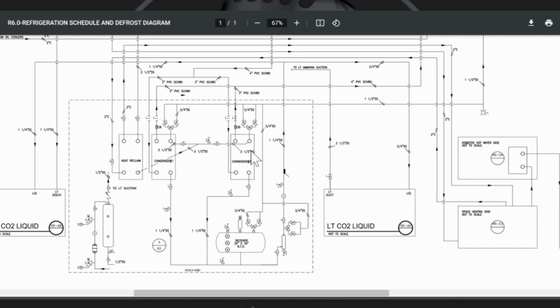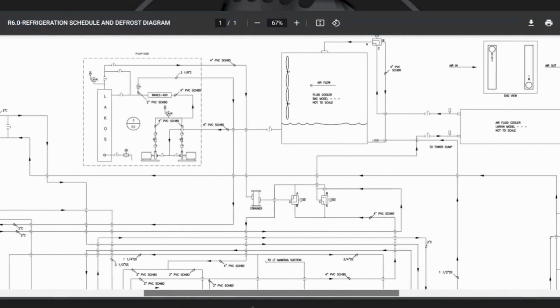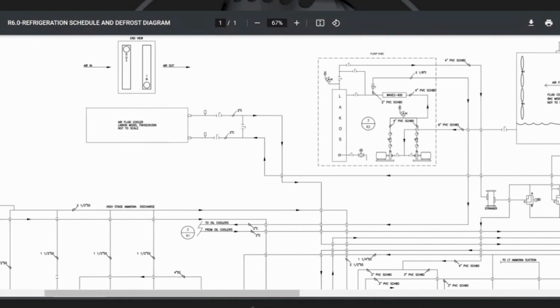So you basically vented it to the inlet of your condensers, I'm assuming. That's correct. We vented it to the inlet of the condenser, and then we insulated the receiver, and the problem went away. Is there anything else you wanted to cover on this that's unique, like this air fluid cooler over here? No, that's the de-superheater air fluid cooler, and that's where we take the heat out year round on the de-superheater circuit.